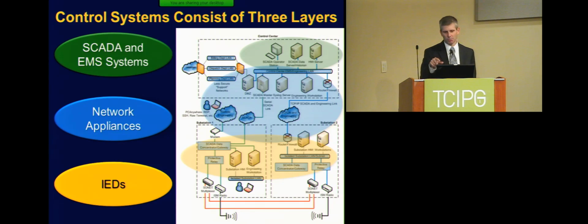There are some more communication links used on the protection side that aren't necessarily directly connected to the SCADA side. We might have a SONET multiplexer connecting all the substations together, sending line current differential information over those links. We may even have a radio link connecting two substations, sending pilot wire communication back and forth.